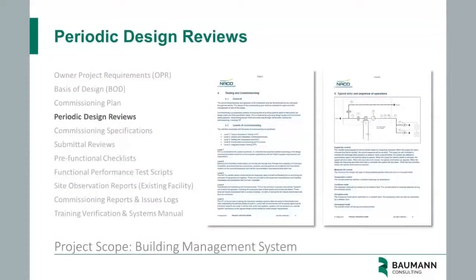We also reviewed the testing and commissioning requirements for the BMS, included in the tender documentation. We had to make sure it adhered to whatever protocols we thought necessary for the BMS contractor once selected. We also reviewed control schematics of the AHUs to ensure all data points - temperature, pressure, airflows, component statuses - were included, along with sequences of operations, making sure these were in accordance with the design requirements.